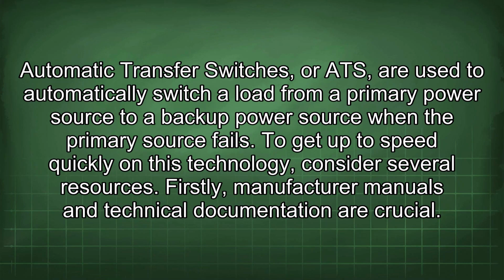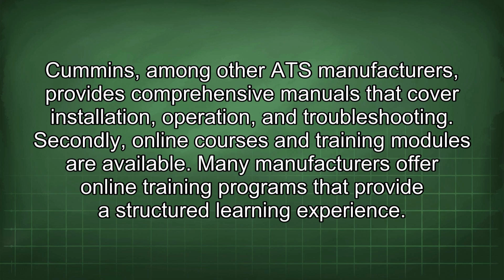Automatic transfer switches, or ATS, are used to automatically switch a load from a primary power source to a backup power source when the primary source fails. To get up to speed quickly on this technology, consider several resources. Firstly, manufacturer manuals and technical documentation are crucial. Cummins, among other ATS manufacturers, provides comprehensive manuals that cover installation, operation, and troubleshooting.